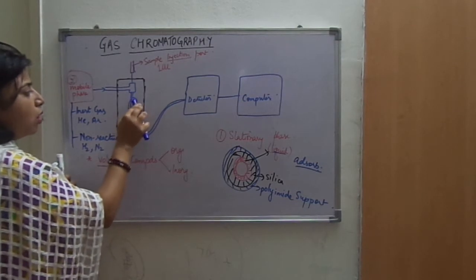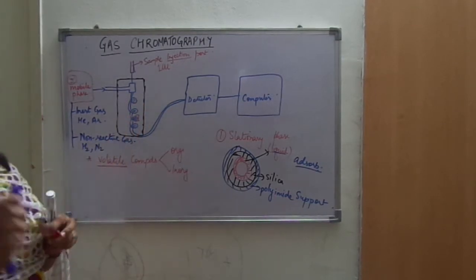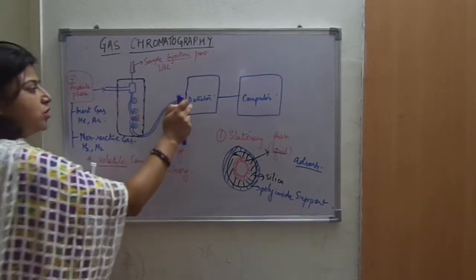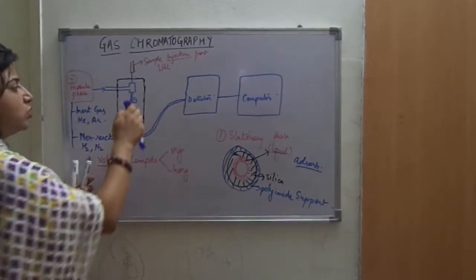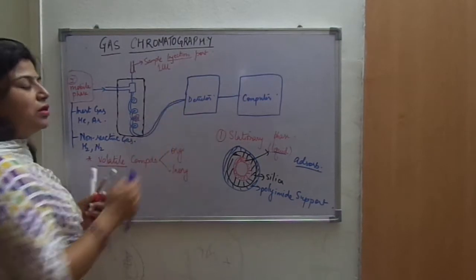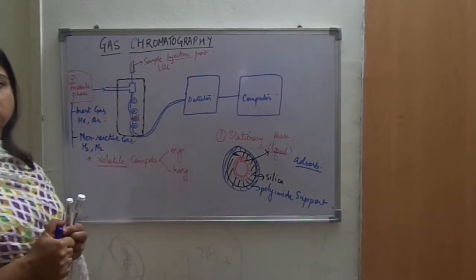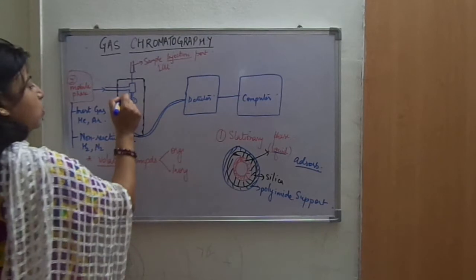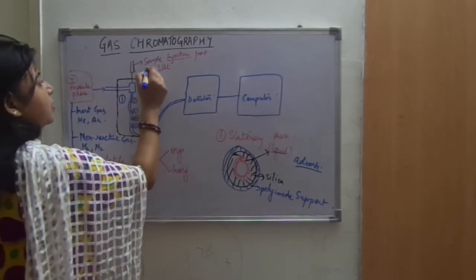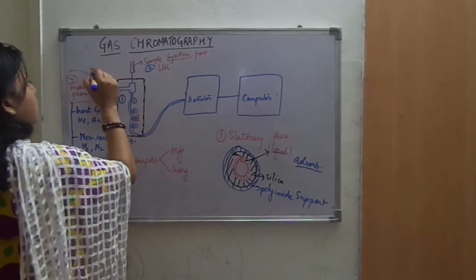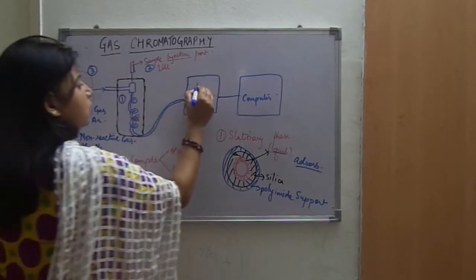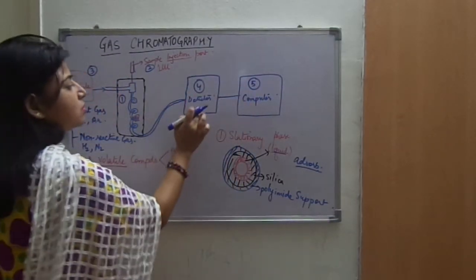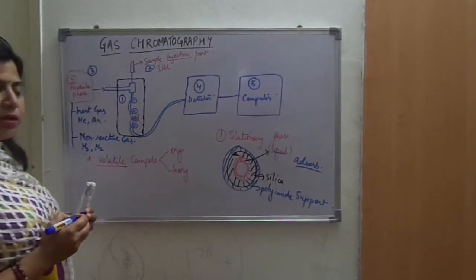The sample component which is pushed first will move the farthest and reach the detector first, and the one pushed least will reach the detector last. The parts of gas chromatography are: first the column, second the sample, third the mobile phase, fourth the detector, and fifth the computer. We will discuss the detector and computer later on.